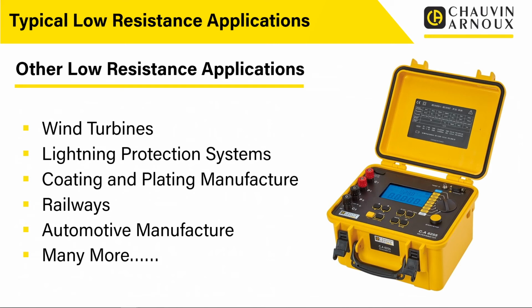I certainly believe there's a lot more application for these in the normal sort of 18th edition BS7671 type installations, particularly when we're looking at bonding connections and bonding conductors. I think having a greater degree of accuracy on those measurements would be very useful. The limit of the accuracy of the testers that we are using is on the edge of what we need, but I don't think it goes that extra step. And from a fault finding point of view, we could diagnose quite a few more things a lot earlier by using low resistance measurements.